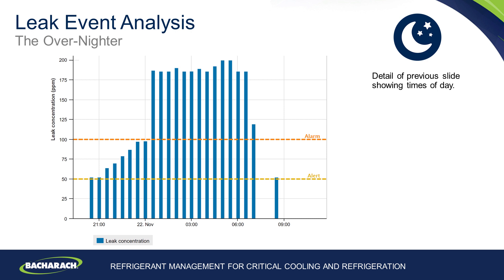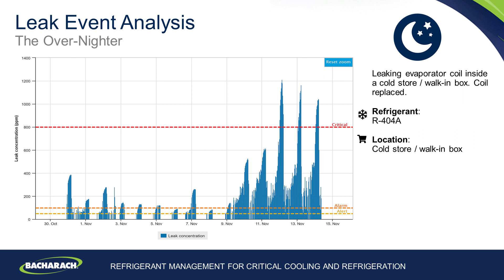From 6am onwards the PPM values disappear as that asset is used by store staff moving goods in and out of it. Here we have another example of a leak inside a walk-in box or cold store. Again you can see the pattern — PPM values rising during the night-time period when the asset is not used and dropping away during the day as the asset is used and PPM values dissipate with airflow.